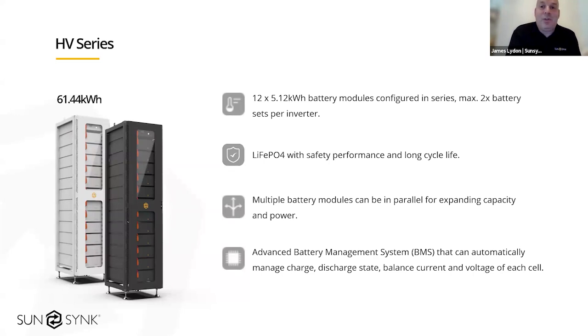And again, on the 30 and the 50, we can have 2 of these racks connected into each 30 or 50 kilowatt hybrid, with 10 of the 30 or 50 kilowatt hybrids connected in parallel. So yeah, massive, massive systems. Again, these are LiFePO4, so really safe battery chemistry, and these are really scalable.